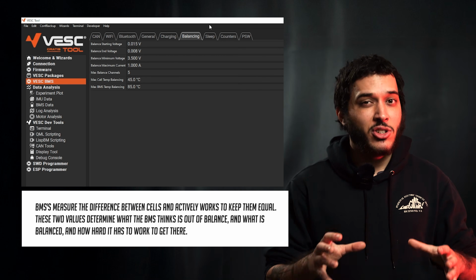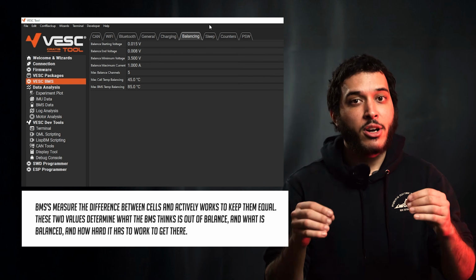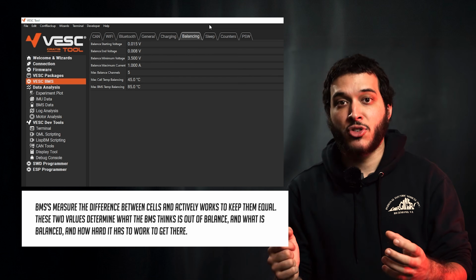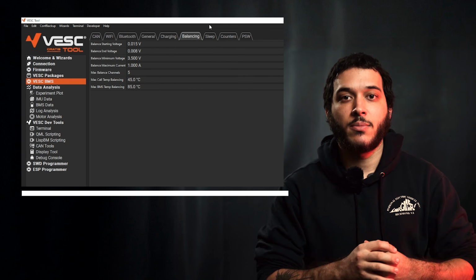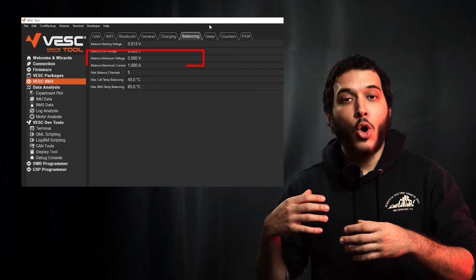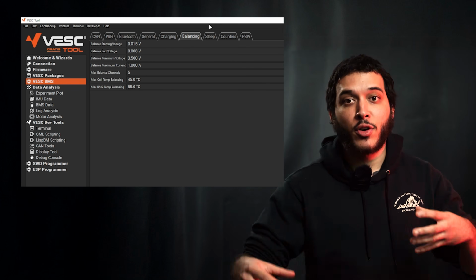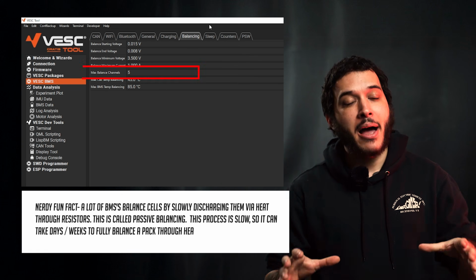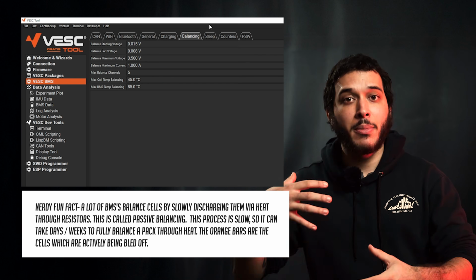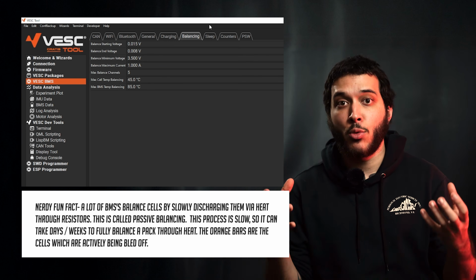Balance end voltage stops balancing when the threshold of 0.008 volts per cell between cells has been met. Balance minimum voltage will only allow balancing to occur above this volts per cell. Max balance channels determines how many cells are allowed to be balancing at one time.